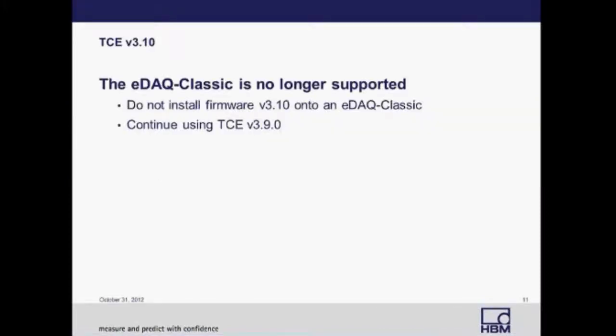Now that we've discussed some of the hardware, let's move on to the TCE software updates. Due to changes in the process starting with version TCE 3.10, all future development of firmware and TCE for the new eDAQ will refer to it as the eDAQ Plus. EDACs prior to the Plus are now referred to as eDAQ Classics and are not compatible with future TCE and firmware developments. Therefore, do not attempt to update your eDAQ Classic with any firmware or use TCE beyond version 3.9.